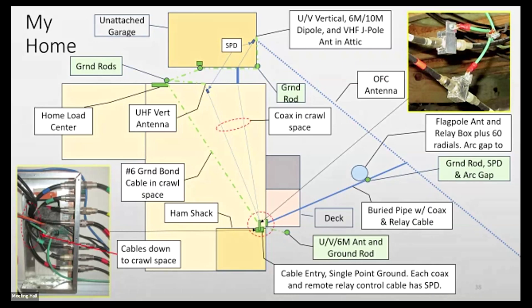Surge protection device right there on the antenna that's mounted off that garage, which I didn't have before. It's there, it's got its own ground rod going down. It's connected to the ground rod of the panel for the garage, which comes over and is grounded to the ground rod and bonded also to the house ground.